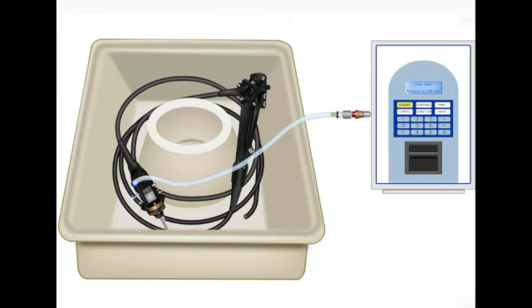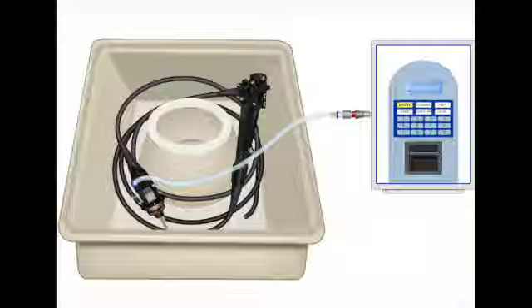So the fate of a $100,000 piece of equipment rests on whether or not the tip puffs out a little bit. That's it. In that second scenario, you only clean it externally. Meticulous wipe down. Then you pack it up and send it for repair, again, following the IFUs to the letter. Incredible. So we've covered the dry mechanical test in detail, but there are other methods. What about the dry manual test? Oh, right. So the dry manual test is often a backup or used in places that might not have the big automated machine. It's more portable.